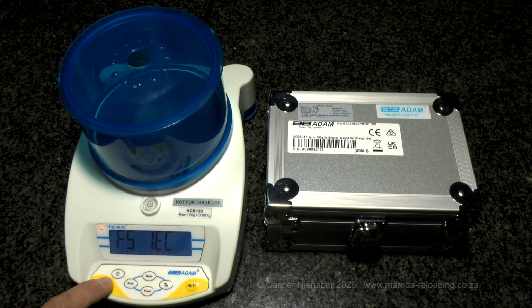Press the yellow Zero Tare button once to display the current calibration weight preference, which is set to INT, internal. Each press of the Mode button toggles between INT, internal, and E, external. Select INT, internal calibration, and save it by pressing the yellow Zero Tare button. This also functions as the Enter key. Press the Print button to exit the calibration selection menu and return to the normal weighing mode.